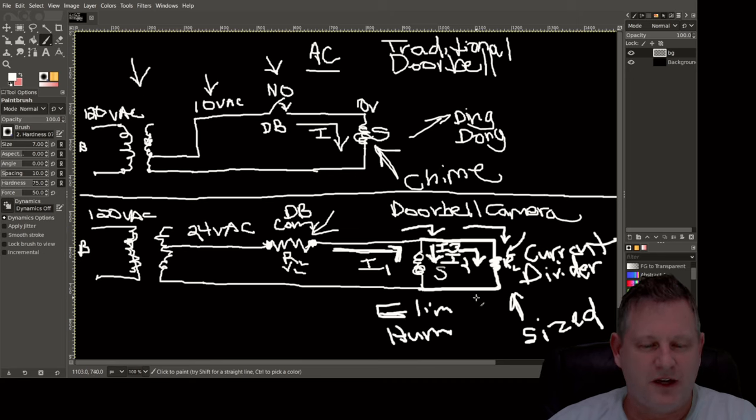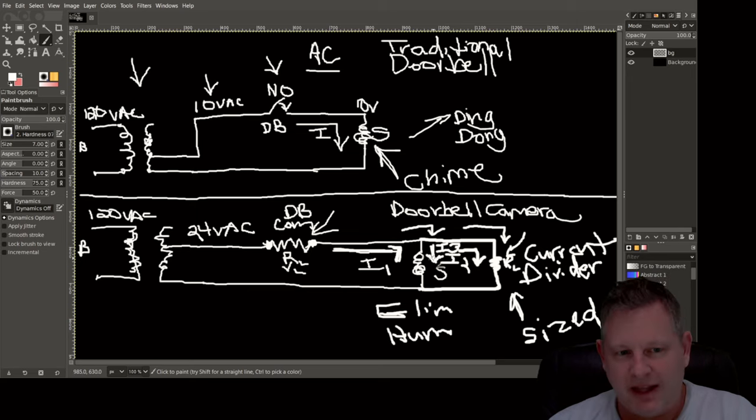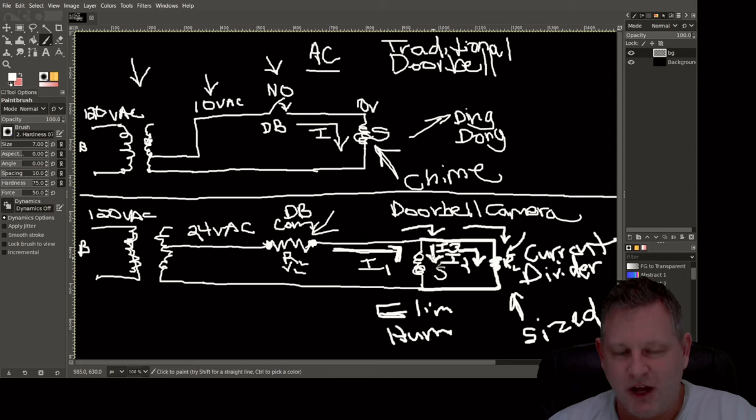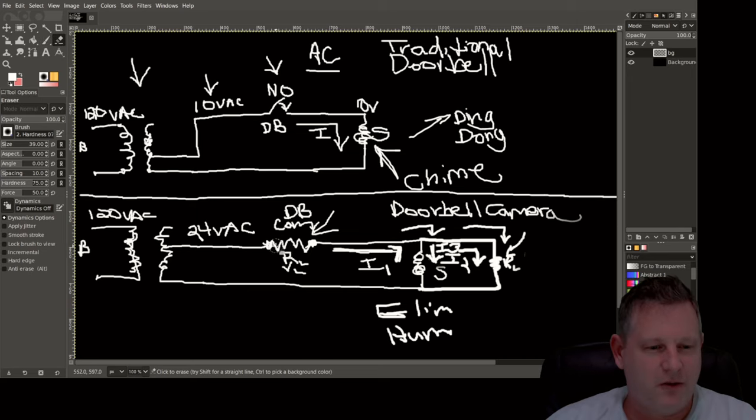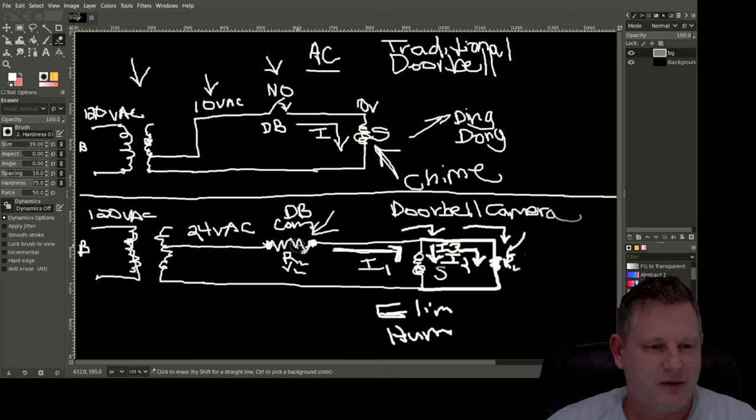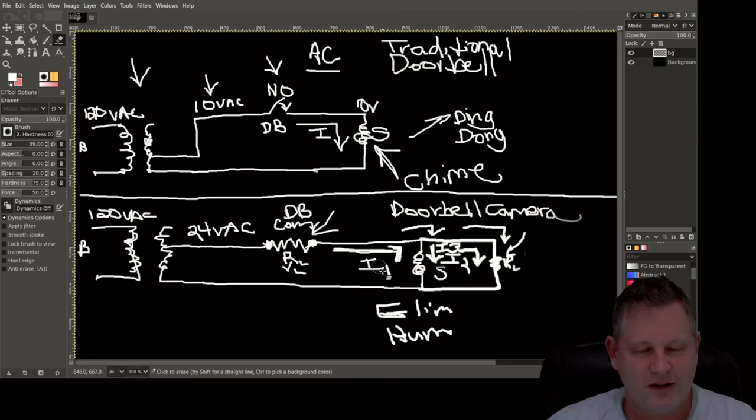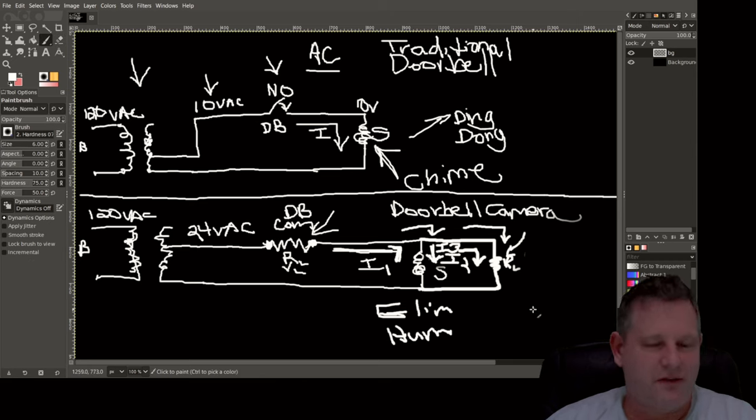Now the purpose of this resistive load here, it is sized, right, so it's sized correctly to eliminate that annoying hum that you would get because current is flowing in a circuit. But now we have reduced the amount of current that is going through this solenoid because we split it. Remember the Kirchhoff's current law? Because we've divided that current across another load that's in parallel with it. That eliminates the hum that you would hear if you didn't have this resistive load in parallel with your solenoid. And that hum is created by the energy in that solenoid. It's not quite enough to actually move the striker, but it's enough to resonate. And that's what you're hearing.